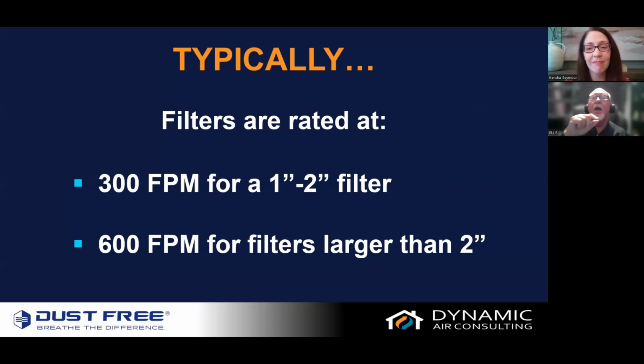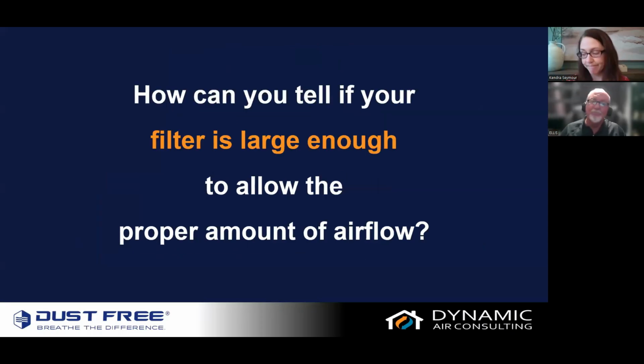Now, if we've got, let's say, a return air filter grille in every room, each one of those can be 1-inch, because they're only handling 300 feet per minute. So we've got 600 feet per minute in a trunk, and then we've got 300 in our branches. So this is important to know, again, that we have to design a filter into the system. We can't just willy-nilly slide something in and hope for the best, but it happens all the time.